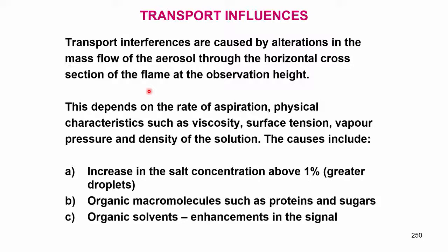So, the transport influences are basically dependent upon the rate of aspiration and physical characteristics. What are the physical characteristics? That is viscosity, surface tension, vapor pressure and density of the solution. For example, if the sample is dissolved in glycerol, the sample uptake will be much lower compared to water, because water has a lower viscosity, and water also has higher surface tension.